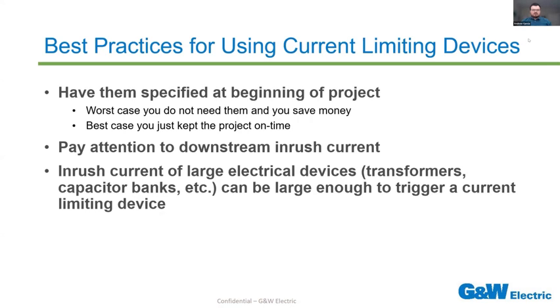So what are some best practices for using these devices? I always recommend having them spec'd in if possible at the start of the project in an ideal scenario. Worst case, you end up not needing them, you end up saving money. Best case scenario, you just anticipated the customer's problem, just kept the project on time. It's also very important to pay attention to sources of downstream inrush current. Inrush of current of large electrical devices such as transformers, capacitor banks, motors, etc. can often be large enough to trigger a current limiting device. So that is something that needs to be kept in mind. Make sure that your devices are coordinated to minimize the risk of that happening.